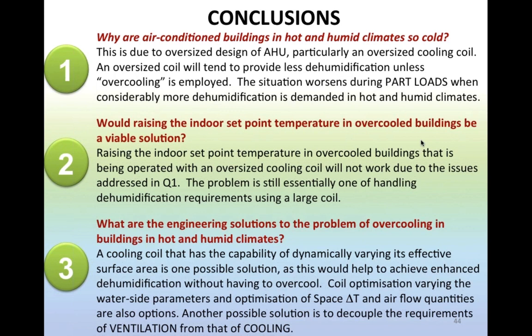So my response is providing that flexibility in the design of the cooling coil and an air handling unit is probably a good idea, and that's what I'm trying to advocate here as a design concept, which will have to be translated through manufactured cooling coils that can get into place. So the consultant, if he says that, well, you are reducing my coil size, I said that's not a problem, because if you actually had your peak cooling load, my coil is no different from your coil.